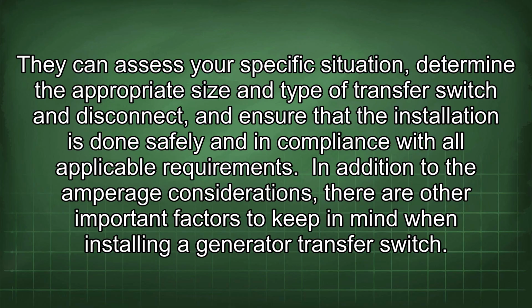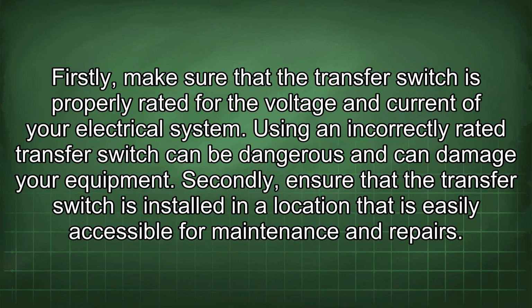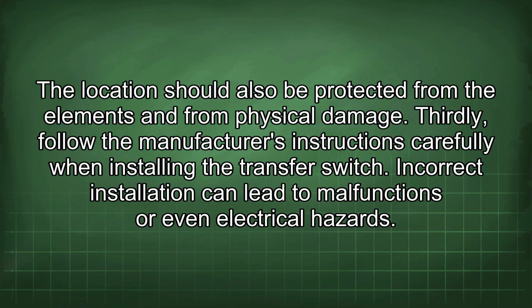In addition to the amperage considerations, there are other important factors to keep in mind when installing a generator transfer switch. Firstly, make sure that the transfer switch is properly rated for the voltage and current of your electrical system. Using an incorrectly rated transfer switch can be dangerous and can damage your equipment. Secondly, ensure that the transfer switch is installed in a location that is easily accessible for maintenance and repairs. The location should also be protected from the elements and from physical damage.